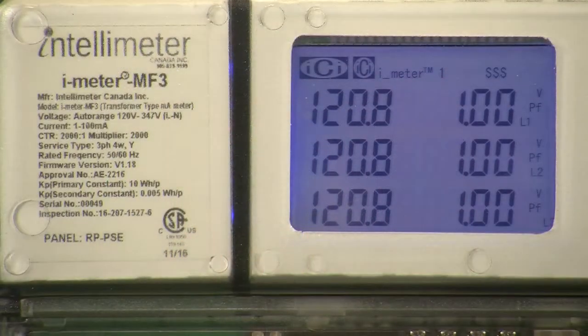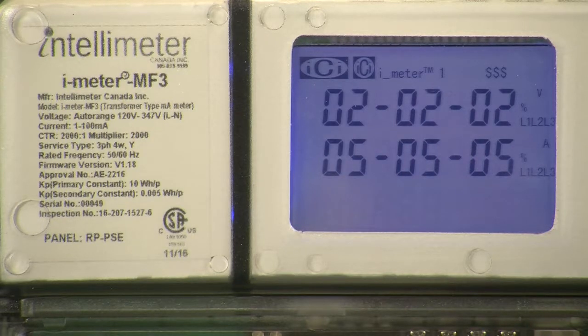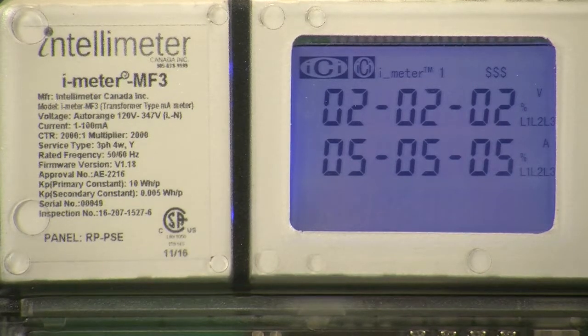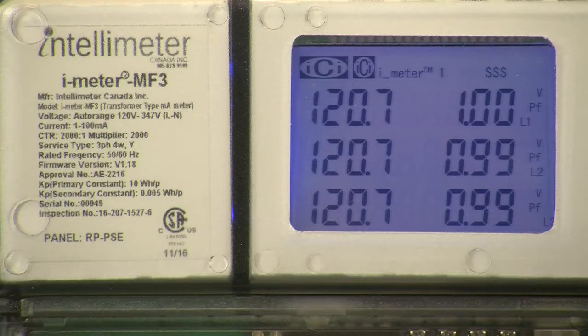As you can see, the iMeter MF3 is now powered up and we have load information showing on the display. The display cycles through many different aspects of information, but from a troubleshooting standpoint, we are mainly concerned with the amperage and power factor. However, in order to perform this troubleshooting, you must first put load on the circuit, breaker, or feeds that you are metering. Any load above 1 amp per phase should suffice.